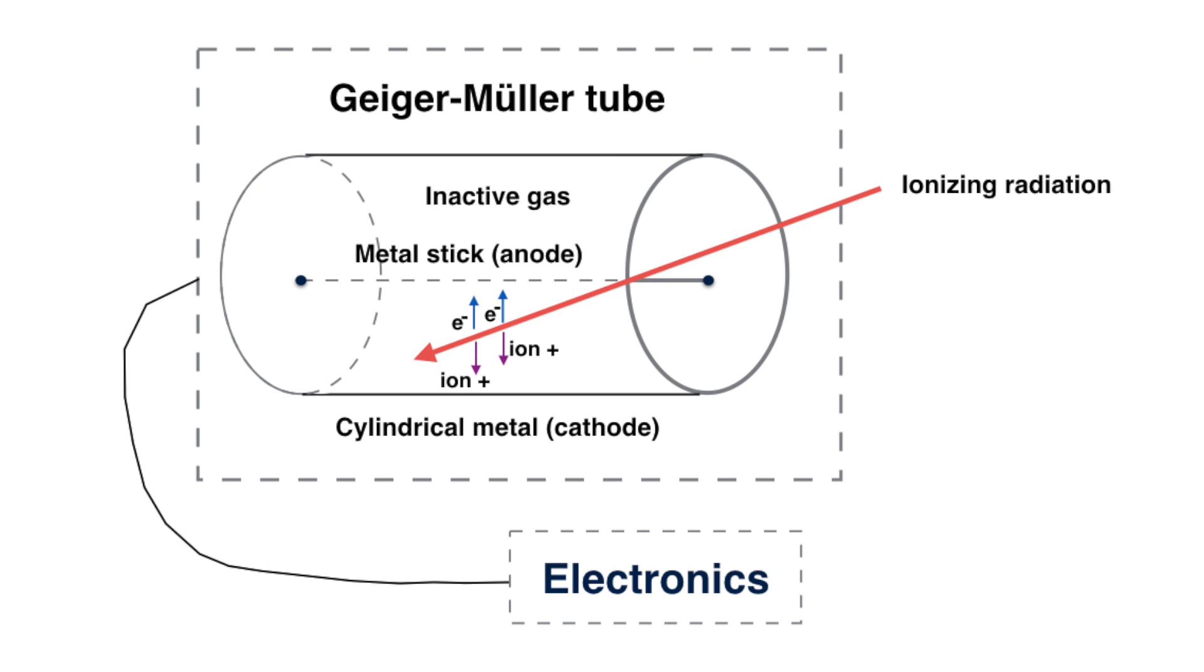The Geiger counter consists of a Geiger-Müller tube, which detects the radiation, and the processing electronics, which displays the result. The Geiger-Müller tube is filled with an inert gas such as helium, neon, or argon at low pressure, to which a high voltage is supplied. The tube barely conducts electrical charge, and a charged particle or photon of incident radiation makes the gas conductive by ionization. The ionization is considerably amplified within the tube by the Townsend discharge effect to produce an instant measured detection pulse, which is fed to the processing and display electronics.